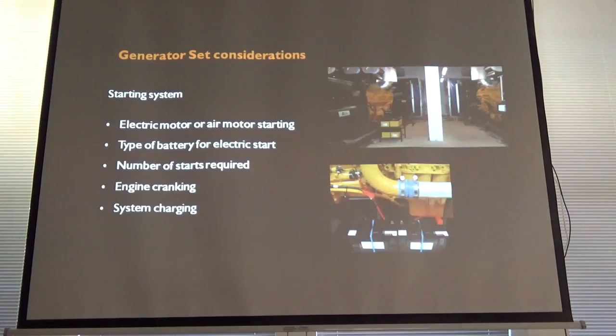Again, all these considerations, which sometimes, until you really look at it and go into detail, you don't see. Electric starting systems. I've never done air starting systems, to be honest, but you can. Batteries are very reliable. Two things you need for a set to start: fuel, batteries. Simple as that. If they're both there and the batteries are sufficiently charged, normal demand is when the jacket heaters are running on the engine, you've also got a trickle charge onto the battery to keep them nicely topped up. Normally after starting, the voltage recovery is over a certain period of time. As a preventative maintenance measure, often they'll monitor the voltage recovery times and start saying, okay, these batteries are on the way out, replace them as a preventative maintenance measure.